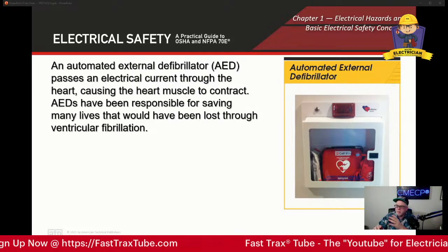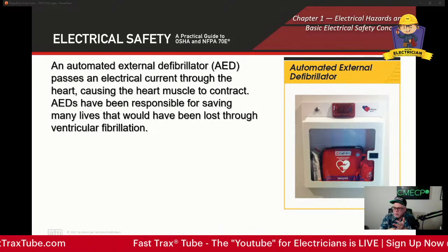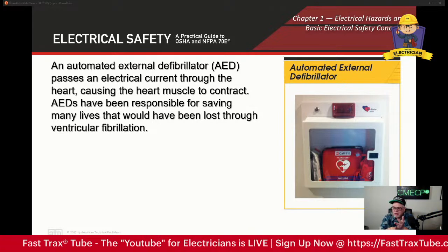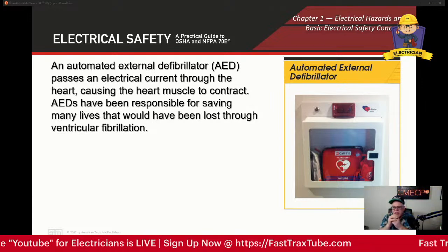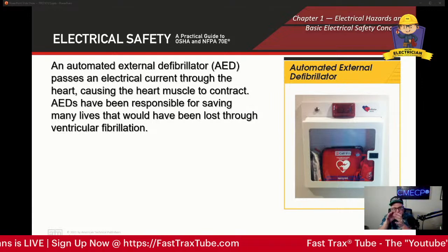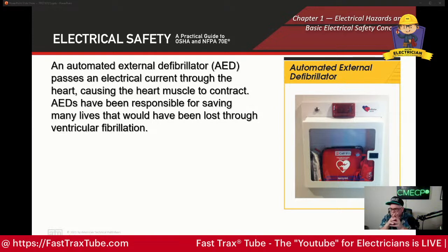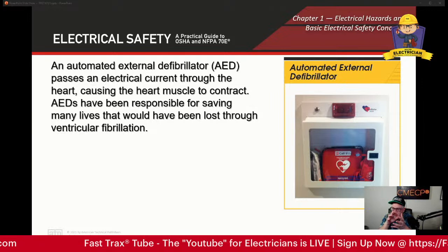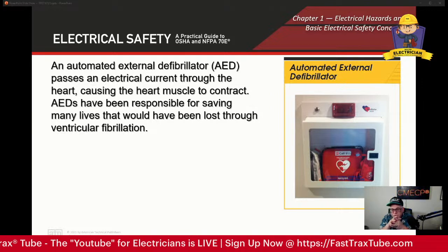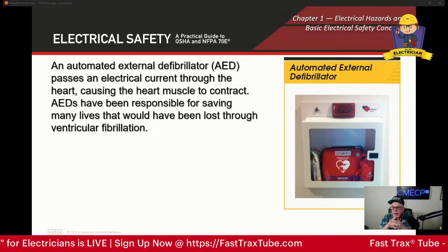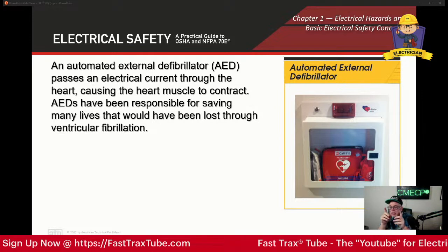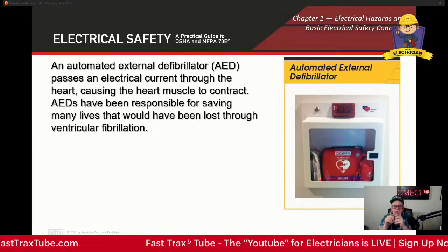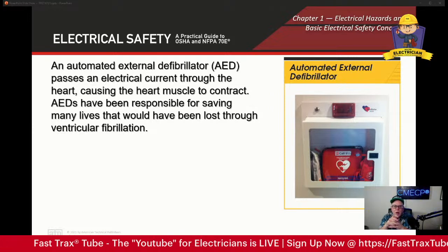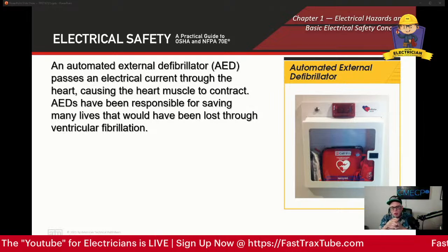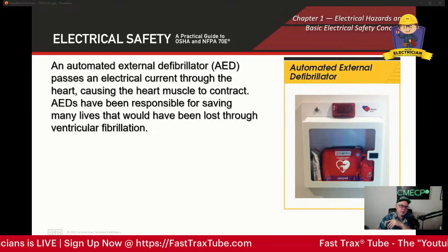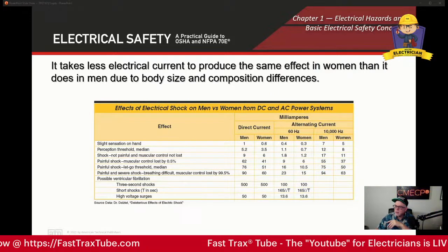So it's pretty simple. It causes a shock, current to pass through the heart, causing the heart muscle to contract and briefly stop, instead of fibrillating, going crazy and not pumping anything. It causes it to stop, and when the current on the machine pulses out and stops, the heart will begin to beat normally again, unless it's been sitting in a fibrillation state too long, in which case it won't do any good. So time is always of the essence for these pieces of equipment.